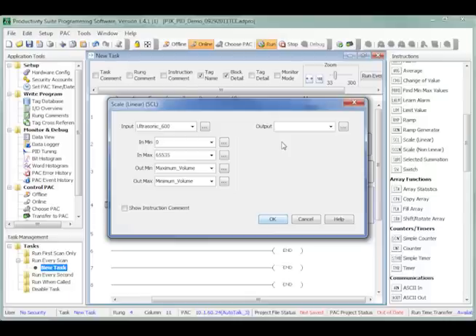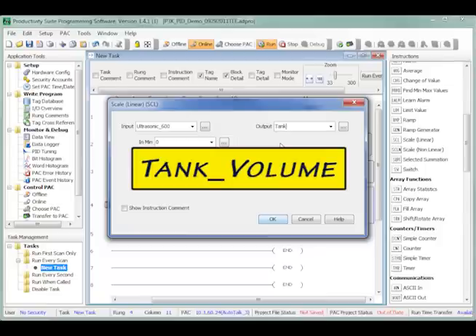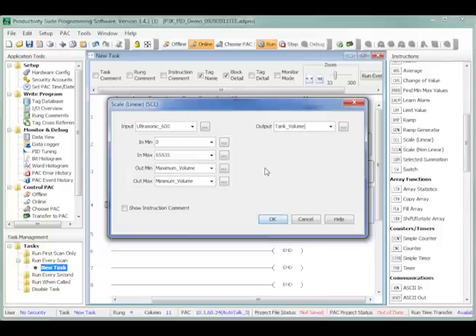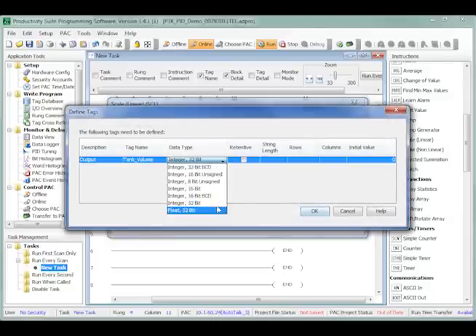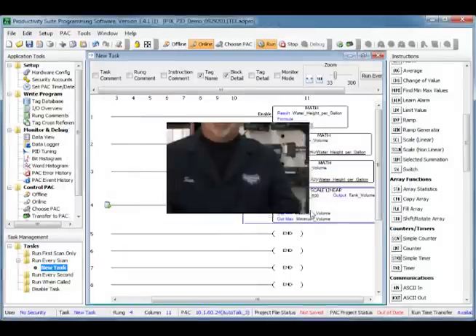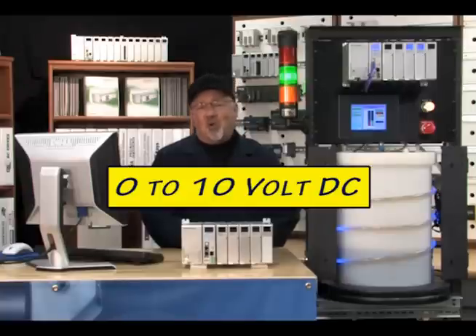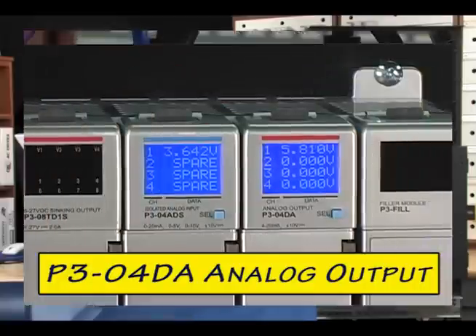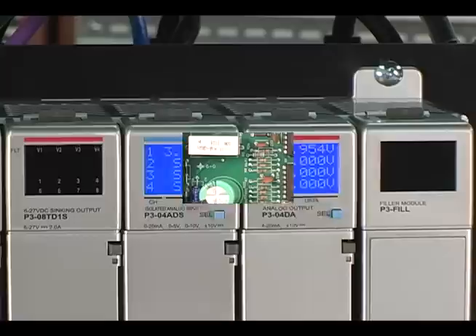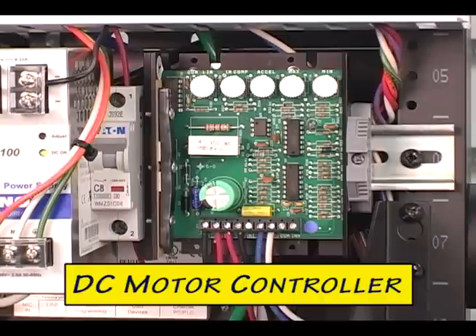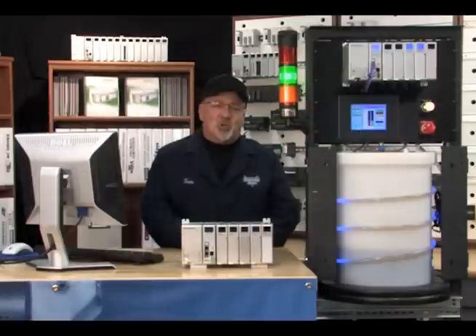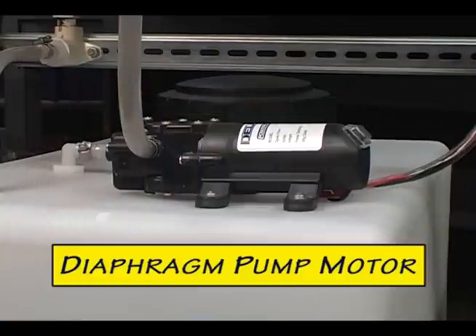Next we need to create another new tag name for our result that goes into the scale instruction's output parameter. We will name this tag name tank_volume. If you have followed along so far, the value in tank_volume will become our process variable used in our PID loop calculations. The output of our PID loop calculation will provide a 0 to 10 volt DC signal from the P3-04DA analog output module to a DART 12 volt DC variable speed motor controller.